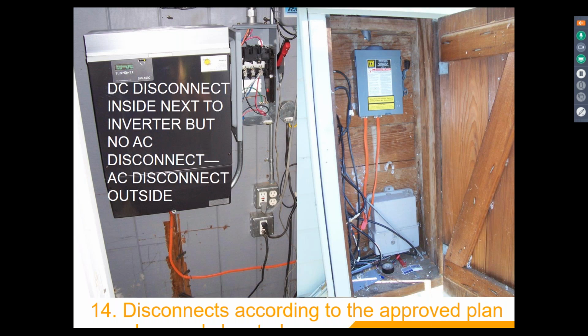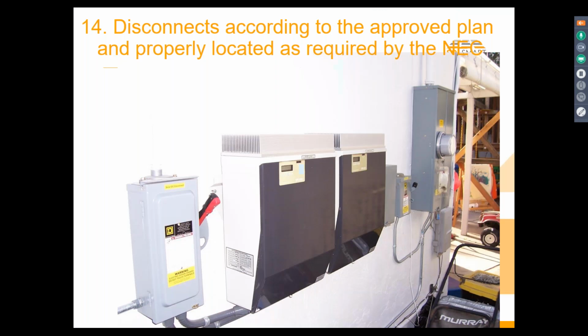Right. So for a DC system like this, a string inverter system like this, pulling the AC switch does zero for safety. All it does is stop the flow of current, but your voltage is still there everywhere. Now, what he said is, in the case of a microinverter system, when you pull that AC switch, it happens to turn off all the inverters, which does make things safer. But the vast majority of the systems, until a few years ago, were string inverter systems. So the firefighter thought they did something. They would come along here and turn that switch off, and they thought they turned off the system. Oh, and then they had another switch here, and they turned that switch off. And then they thought they did something. Neither one did anything to improve safety.